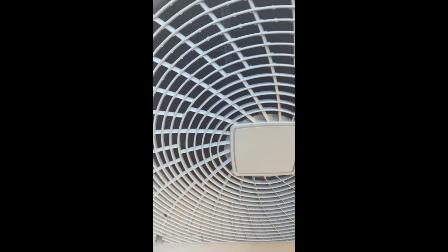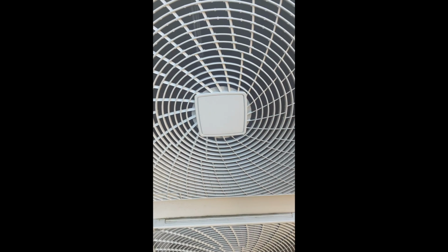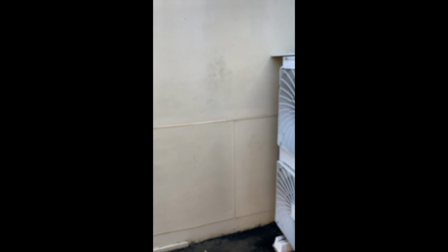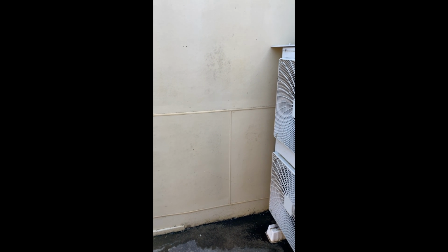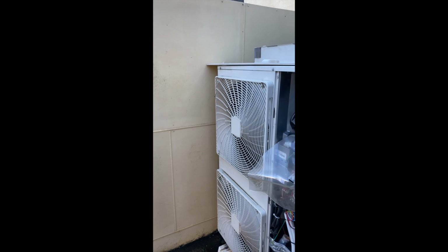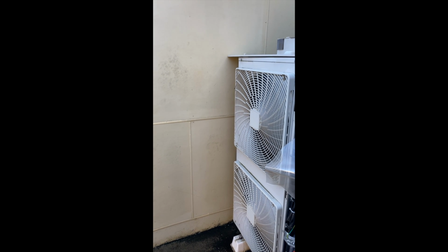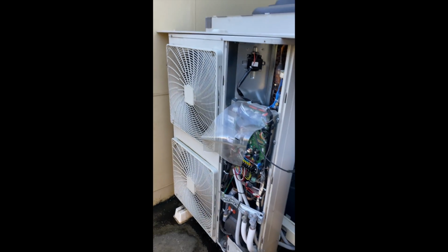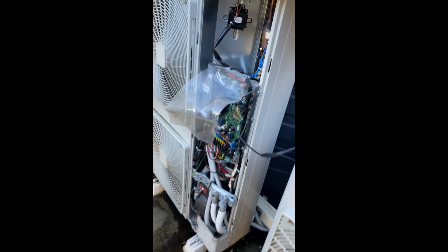Fan is now blowing. Sometimes what happens here is this is actually blowing out warm air, and you can see that my camera has just fogged over. At times after defrost you actually see a puff of steam coming out the front of the unit because it is blowing warm air into really cold outside air. So if it's like -2 outside and the coil is at like 2 or 3 degrees and moist because it had just melted ice, you'd actually see a big puff of steam coming off the front of the unit. We've had people ringing up saying, oh, my air conditioner's on fire. But it's not really, it's just a bit of steam.